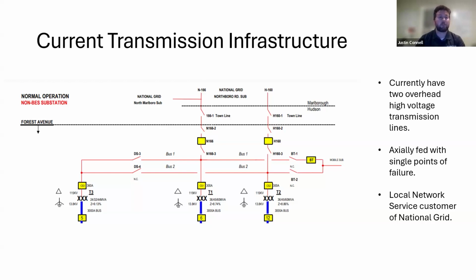As a utility, we always like to look at contingency and follow at least an N+1 contingency, meaning that if we lost one feed, one line, or one piece of equipment, we always have at least one additional route to maintain business continuity. This setup has met that for a long time. These lines went in back in 1977, and in the early 2000s we did a significant upgrade in the substation as it sits today. But these lines are radially fed from one direction and dead-end with us, and at some points they're on single transmission poles, so we do have single points of failure in our feed into the system.